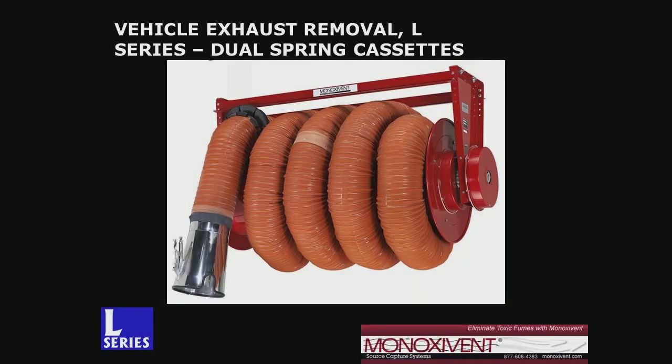Okay, next we have our dual spring cassette. And the dual spring cassette is designed to bridge the gap between your standard spring cassette and your motorized hose reels. In most instances, when you get into larger diameter hose, some 8-inch applications, and certainly anything larger than that, you need to move to a motorized hose reel because it can handle more weight. Your hose is heavier, your tailpipe adapters will be heavier. So with that being said, it's also more expensive. Motorized hose reels are more expensive than spring hose reels.